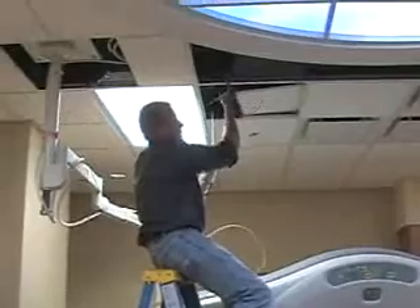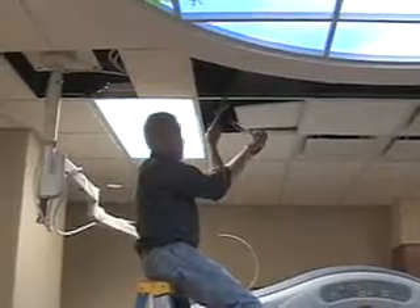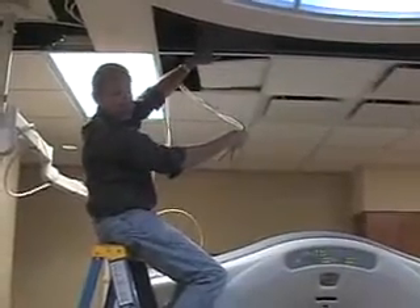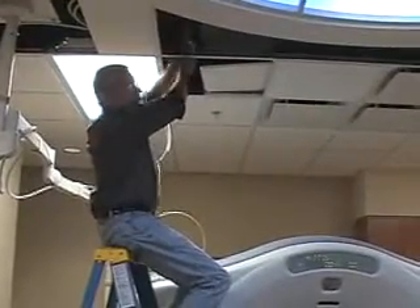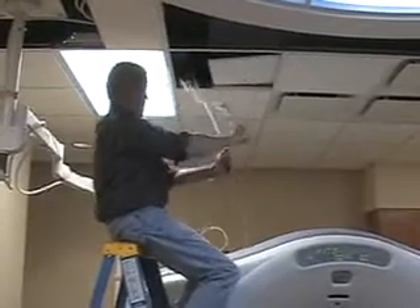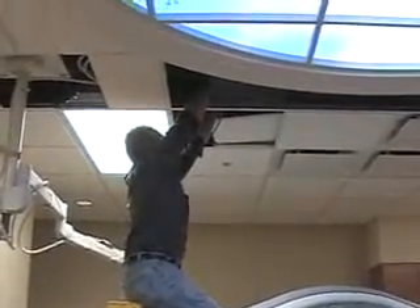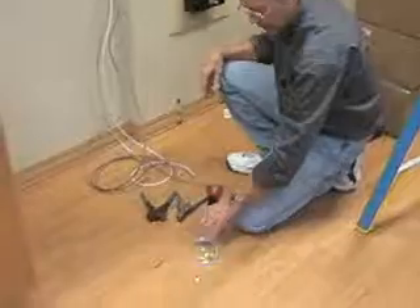Okay, we need enough cable. This is the cable from the computer room, and here are the cables from the Z1 side, and here are the cables from the Z2 side. We need about this much, right here, because we need to get to this end of the plate. This is where the X-arm, which is going to be mounted up here, is wired in. So we'll make it about the same length. Then we'll take the tape off, strip the ends of all of these cables, put the connectors on, and we'll show you the connectors going on in just a few minutes.